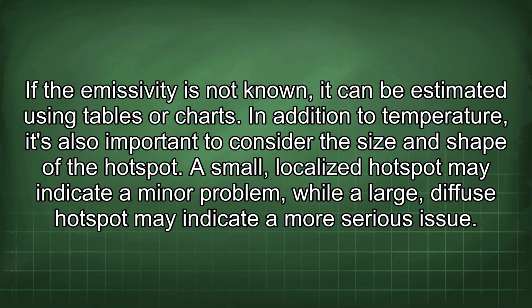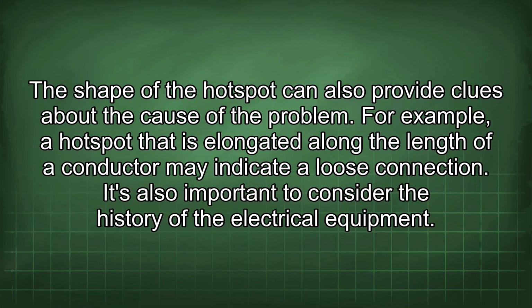In addition to temperature, it's also important to consider the size and shape of the hotspot. A small, localized hotspot may indicate a minor problem, while a large, diffuse hotspot may indicate a more serious issue. The shape of the hotspot can also provide clues about the cause of the problem. For example, a hotspot that is elongated along the length of a conductor may indicate a loose connection.